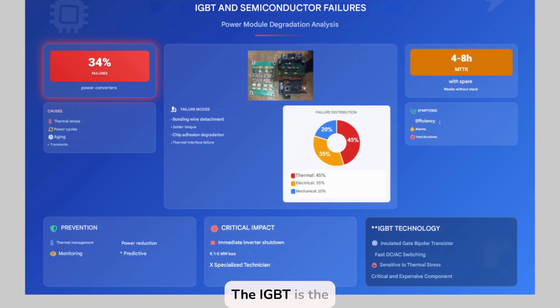The IGBT is the electronic heart of the solar inverter, and as such, if it fails, the entire system collapses. Preventing its failures is not just a technical advantage or an improvement in maintenance, it's a financial and operational obligation. Because an unforeseen failure can cost much more than a simple repair, it can jeopardize the overall profitability of the project, affect the fulfillment of a PPA, and damage the operator's image with the end customer.